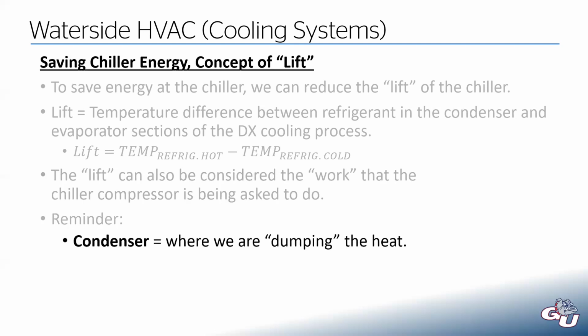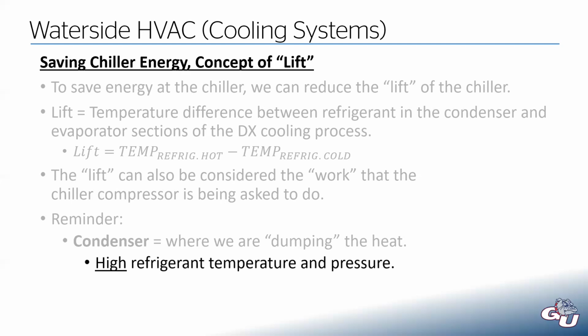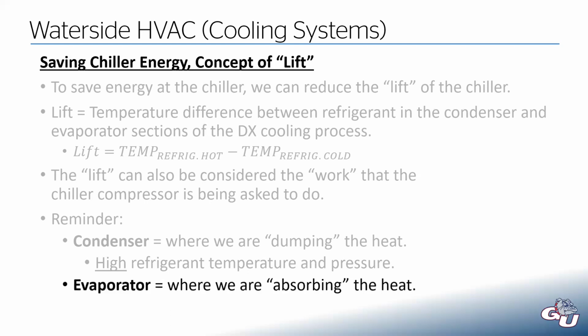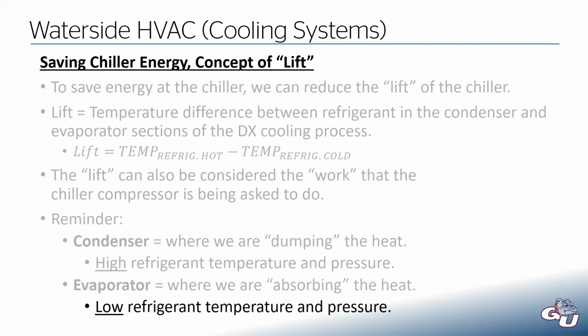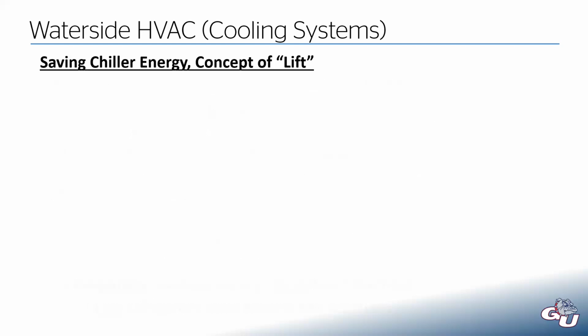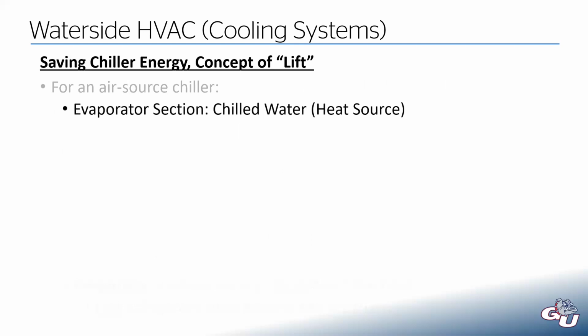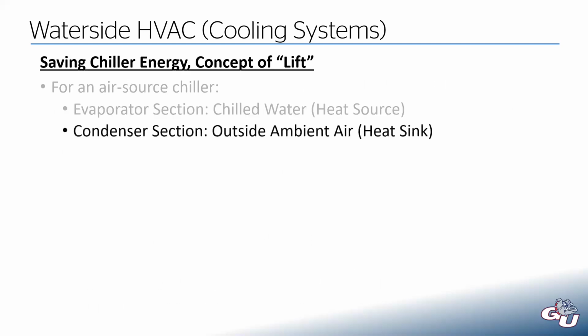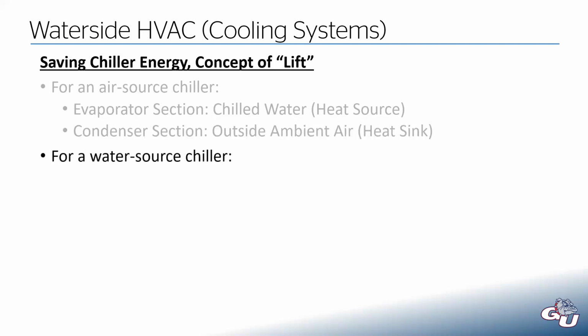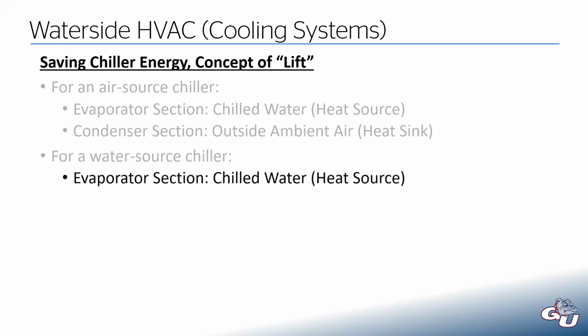As a reminder, condenser, that's where we're dumping the heat. So that would be our high refrigerant temperature and pressure. The evaporator is where we're absorbing the heat. So that would be the low refrigerant temperature. For an air source chiller, the evaporator section is our chilled water. That's our heat source. That's where we're pulling heat from. And the condenser section is our outside ambient air. That's our heat sink. For a water source chiller, the evaporator section is still the chilled water.